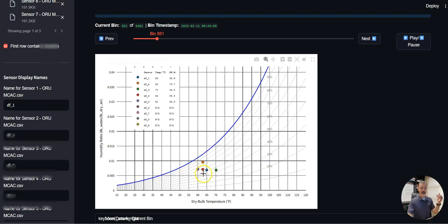But this sensor especially, and even all these others, end up climbing. So anyways, this sensor right here is actually in the gymnasium space, so it's not going to track.